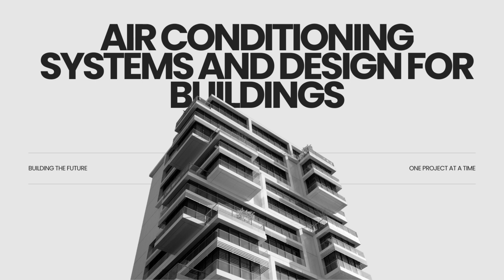Third, we have ceiling suspended units. As the name implies, these hang below the ceiling structure, often visible. They're used when there isn't enough space above the ceiling for a cassette, or when a more powerful, longer air throw is needed for larger, open-plan spaces like warehouses, workshops, or gyms, where aesthetics might be less critical than powerful, uniform air delivery. So function over form sometimes. Pretty much. And fourth, there are floor-mounted units. These sit on the floor, often against the wall, looking a bit like a modern radiator.